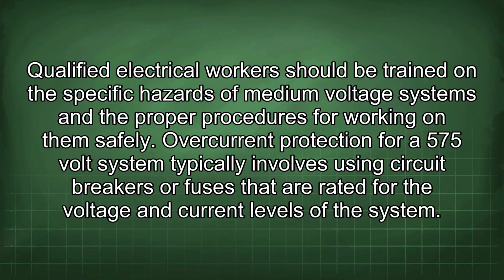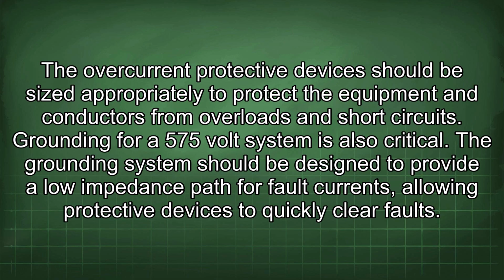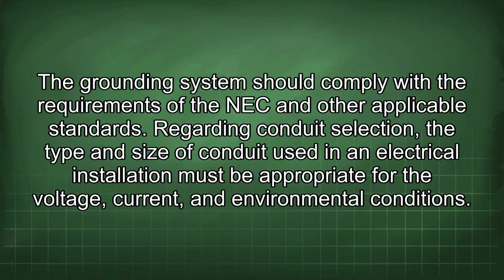Overcurrent protection for a 575-volt system typically involves using circuit breakers or fuses that are rated for the voltage and current levels of the system. The overcurrent protective devices should be sized appropriately to protect the equipment and conductors from overloads and short circuits. Grounding for a 575-volt system is also critical. The grounding system should be designed to provide a low impedance path for fault currents, allowing protective devices to quickly clear faults. The grounding system should comply with the requirements of the NEC and other applicable standards.